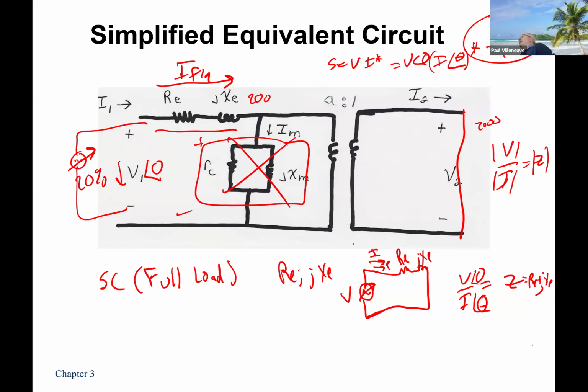Way easier. Most of you don't realize because you've been doing stuff in a paper environment. But when you calculate something and you've got to run 2000 amps of current, you're running multiple 1-inch diameter cables per phase. You're running like 5 or 6 cables per phase. That's a lot of copper. That's a lot of money. Where for 200 amps, you could probably get by with like a number 4, maybe a 4-aught cable. So you can get by with a single one. So these short circuit tests or load loss tests are always performed on the high voltage winding. You put the equipment on that side and you short out the low side. So that's the full load test.